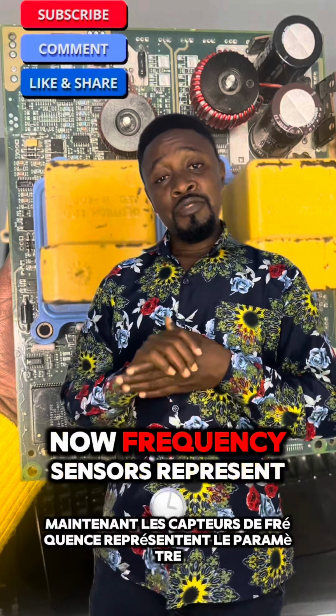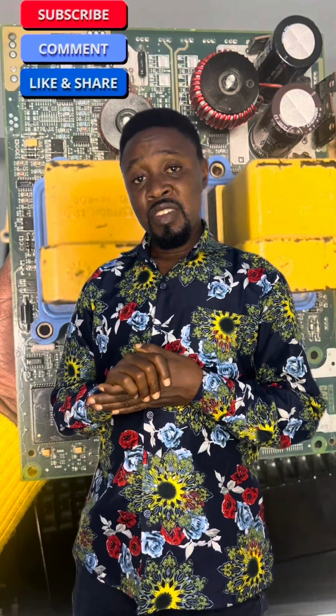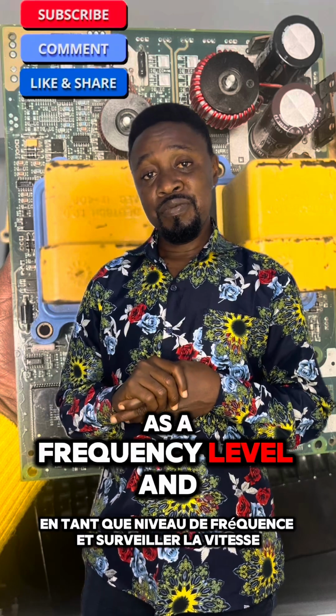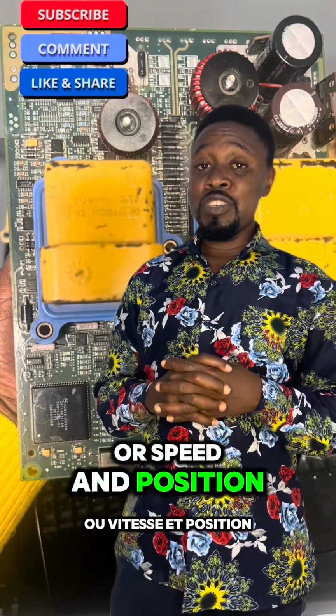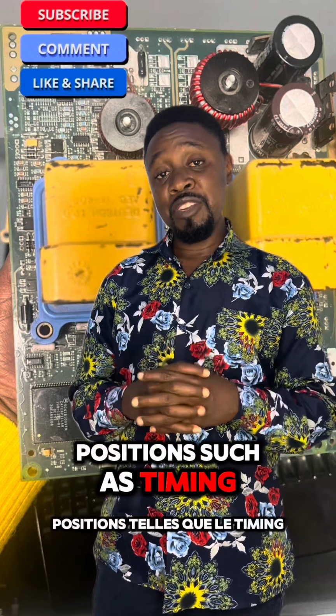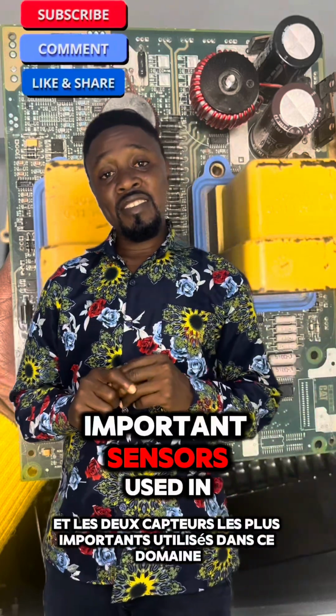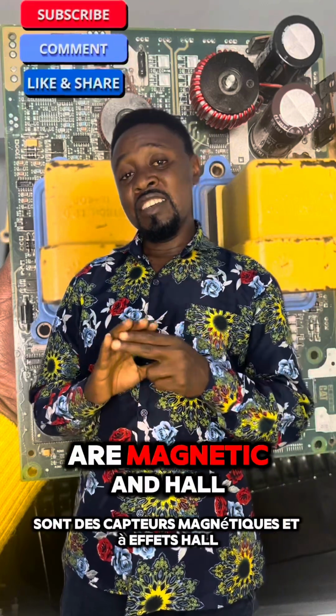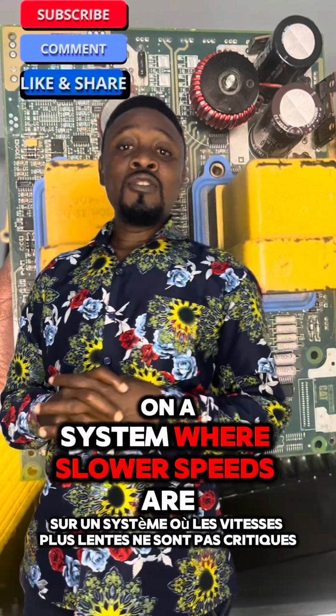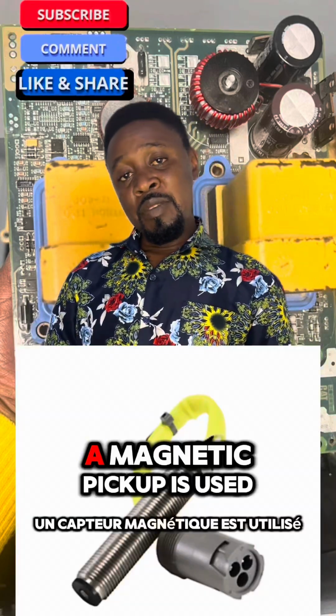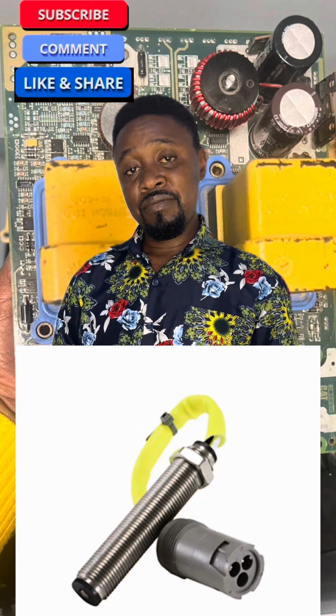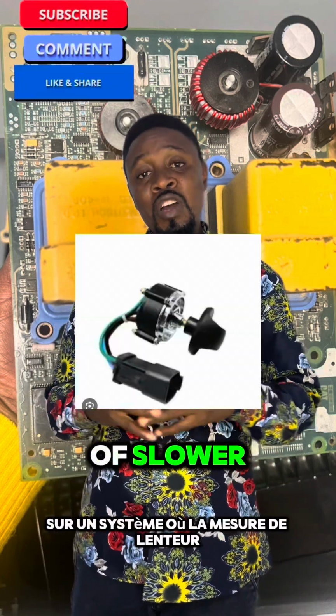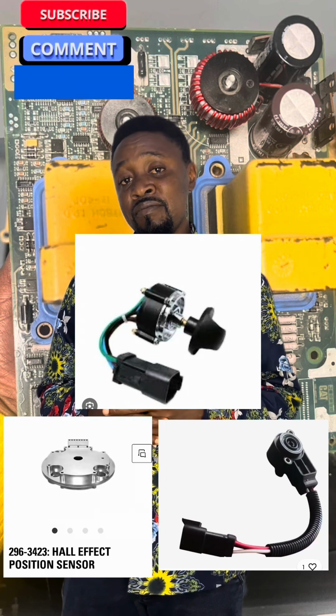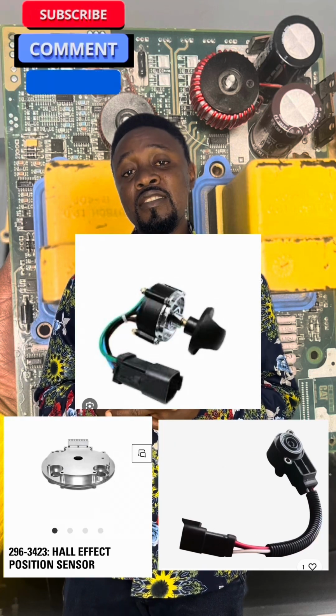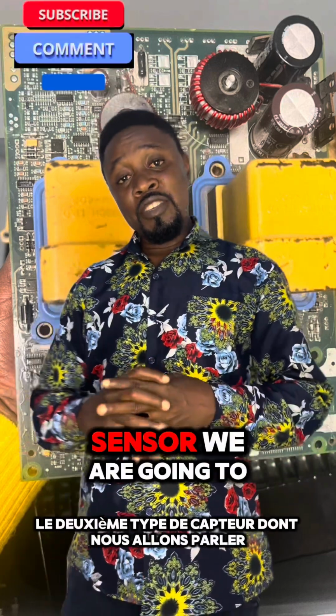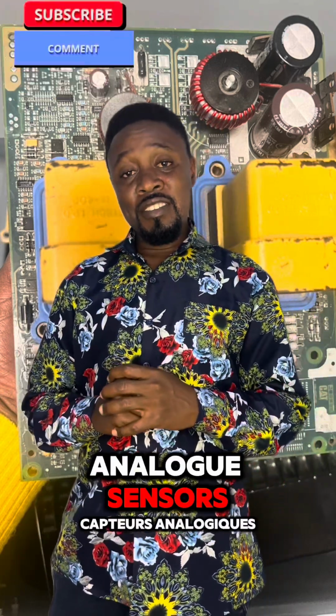be identified. Now, frequency sensors represent the parameter as a frequency level and monitor speed and positions such as timing. The two most important sensors used in this field are magnetic and Hall effect sensors. On a system where slower speeds are not critical, a magnetic pickup is used. On a system where measurement of slower movement is essential, the Hall effect sensor is used.